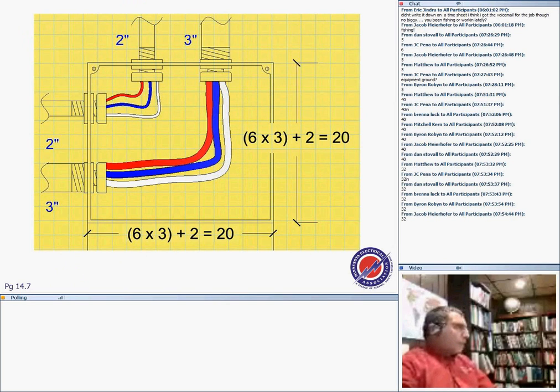The other thing is that the code also says the distance between conduits containing conductors, where you drill the hole here and here, must be maintained. For this one, it's 6 times the largest, which is 2, so that gives 12 inches here. The edges of the two holes cannot be closer than 12 inches. The same thing: 6 times the largest conduit, which is 3, is 18. This distance here cannot be less than 18 inches. This applies only to conduits that contain the same conductor. Minimum distance between them is 6 times the largest conduit.